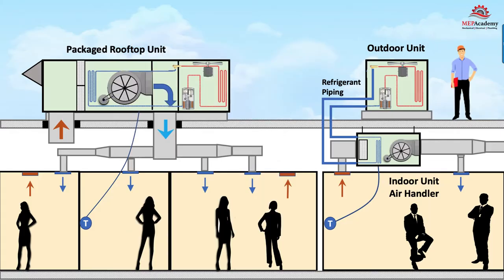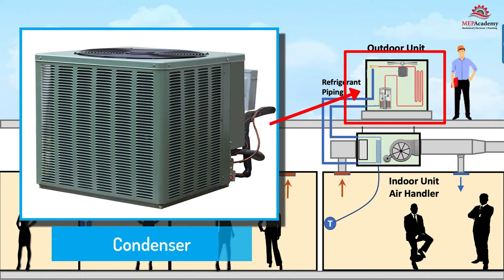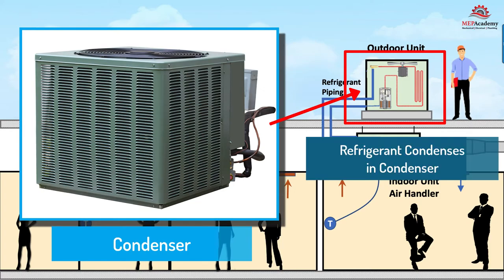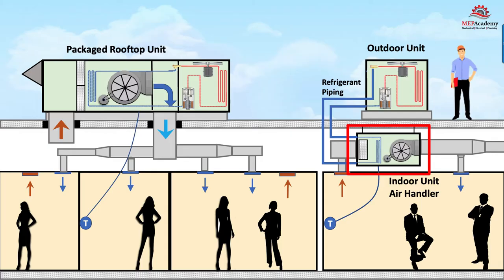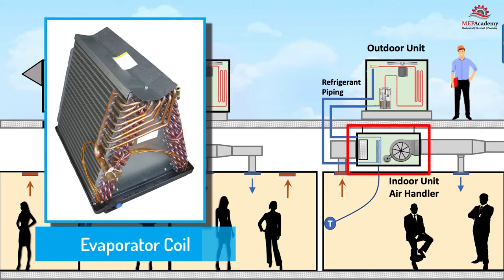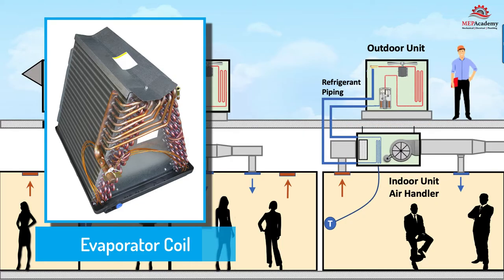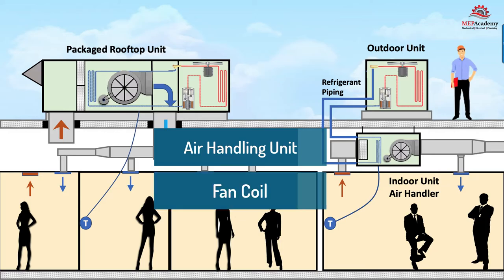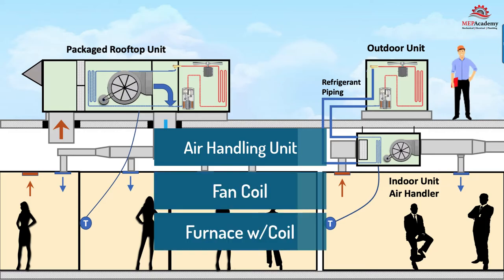The split system is made up of the outdoor unit, often called the condensing unit because this is where the refrigerant condenses from a gas back into a liquid, and an indoor unit where the evaporator is located. The indoor unit can be called an air handling unit, AHU, fan coil, or a furnace with coil.